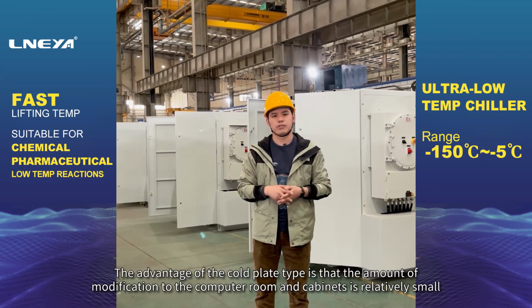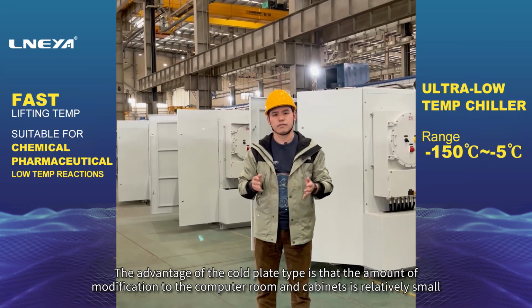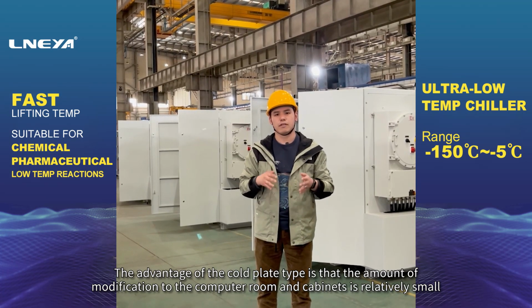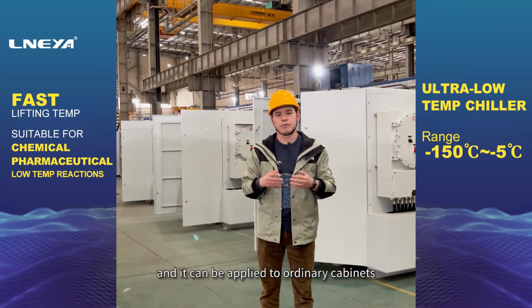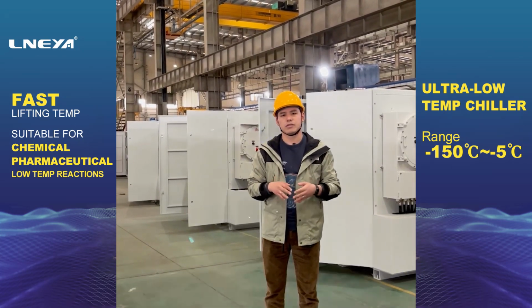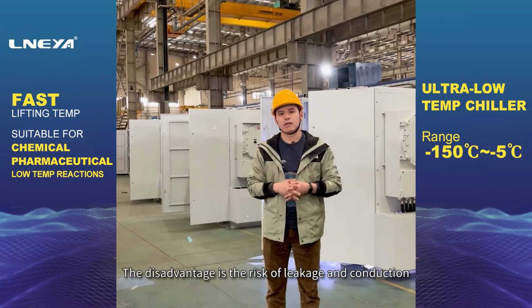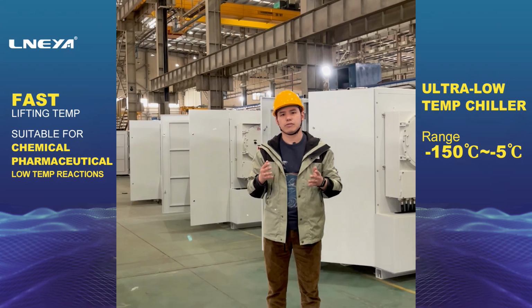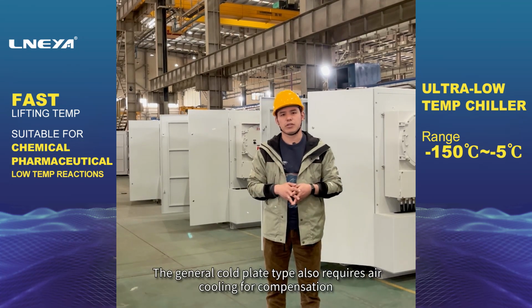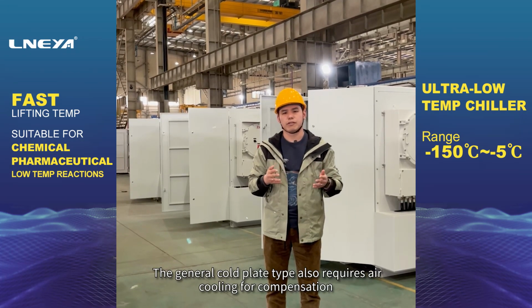The advantage of the cold plate type is that the amount of modification to the computer room and cabinets is relatively small, and it can be applied to ordinary cabinets. The disadvantage is the risk of leakage and conduction. The general cold plate type also requires air cooling for compensation.